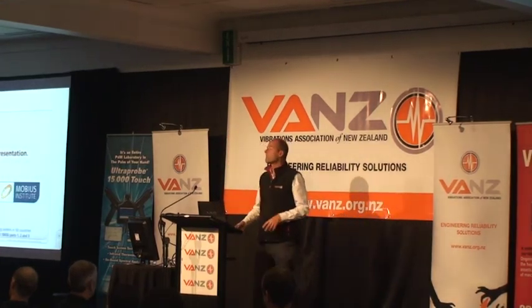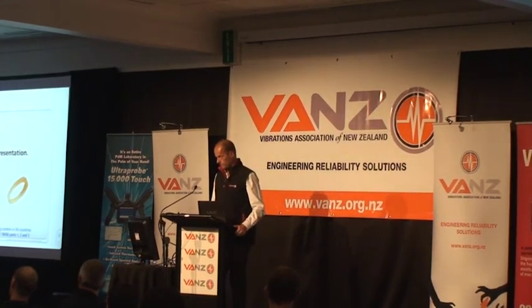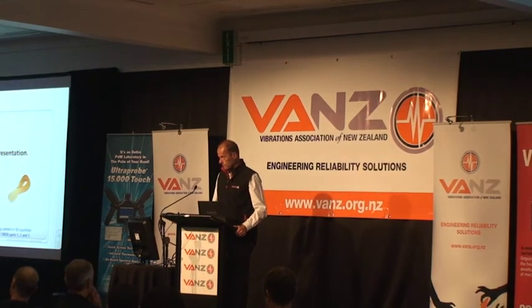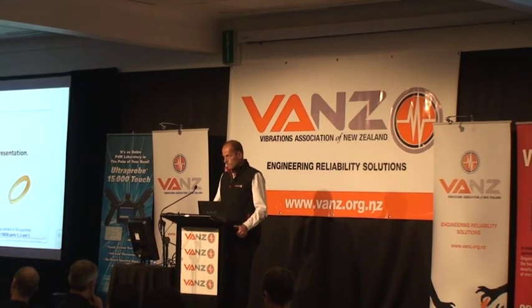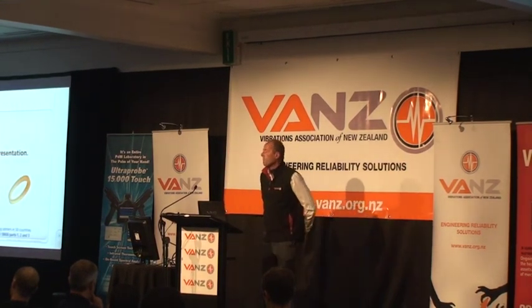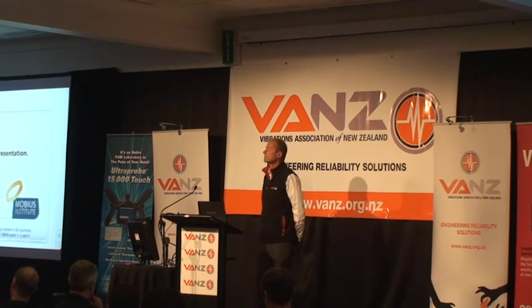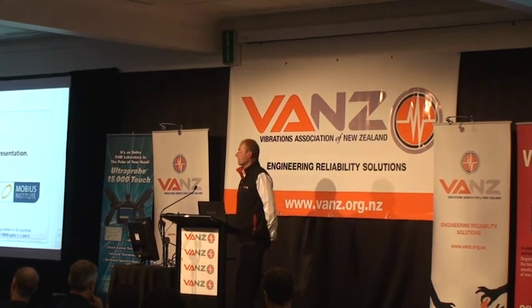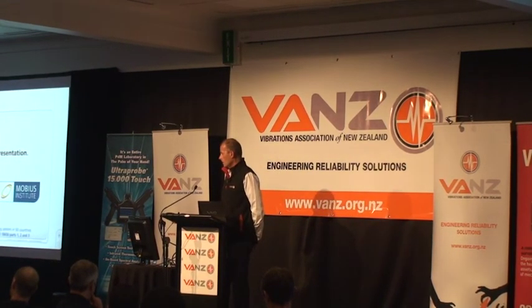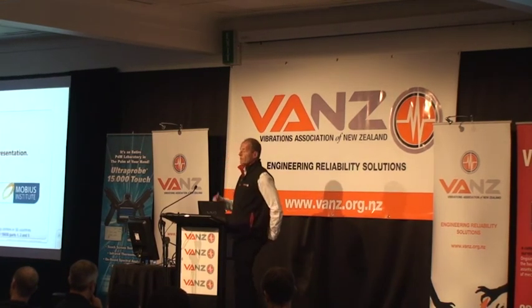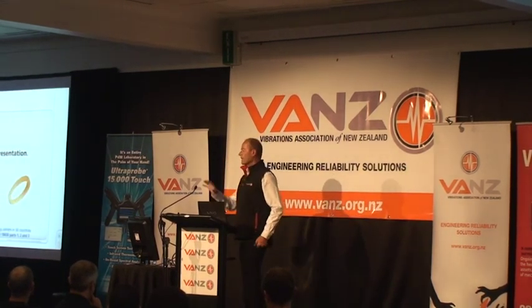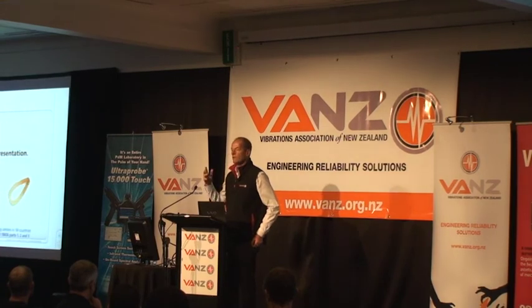Yeah, Jason, I'd like to make one comment on the type of instrument or the sensor itself. It's pretty much looking into the material. It's not really staying at the surface. So if you have some material inhomogeneity, it will give you a false reading of an actual change of the distance. So it's another point just to keep in mind, even if it's perfectly circular, so to say. Well, that's what the glitch removal's for. Yeah. So any non-homogeneity, try and say that a few times.